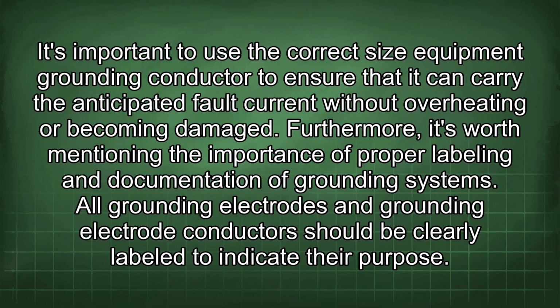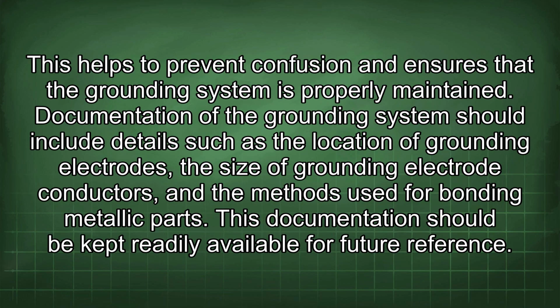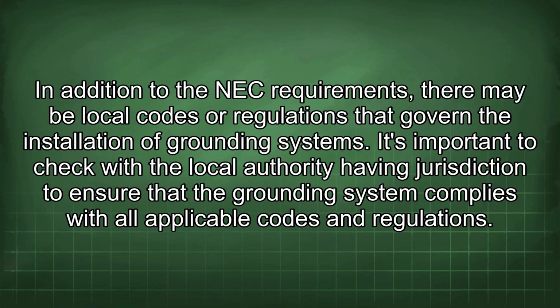Furthermore, it's worth mentioning the importance of proper labeling and documentation of grounding systems. All grounding electrodes and grounding electrode conductors should be clearly labeled to indicate their purpose. This helps to prevent confusion and ensures that the grounding system is properly maintained. Documentation of the grounding system should include details such as the location of grounding electrodes, the size of grounding electrode conductors, and the methods used for bonding metallic parts. This documentation should be kept readily available for future reference. In addition to the NEC requirements, there may be local codes or regulations that govern the installation of grounding systems.